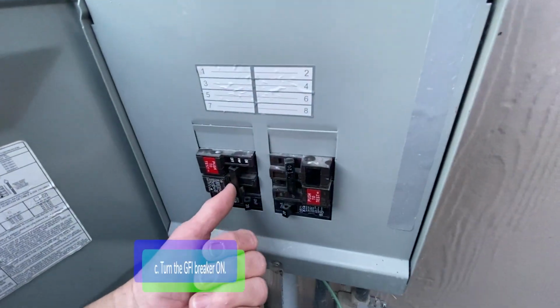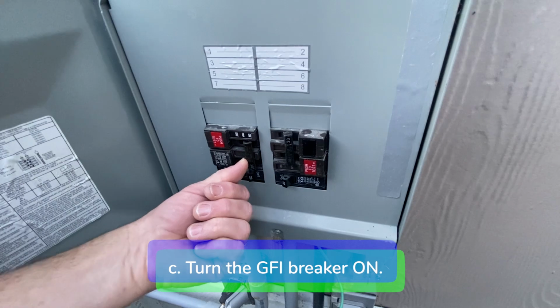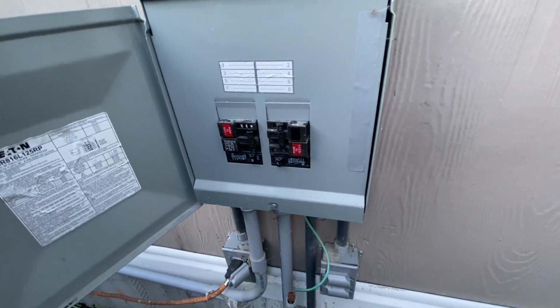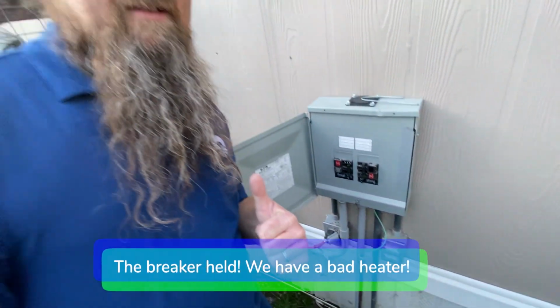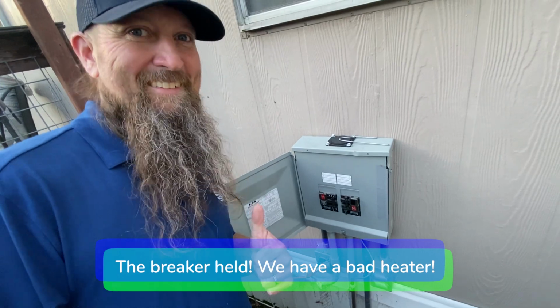C. Turn on the breaker. If the breaker holds, it means the component you disconnected is bad and must be replaced. If the breaker trips, it means you need to move on to the next component. The breaker held. We have a bad heater.